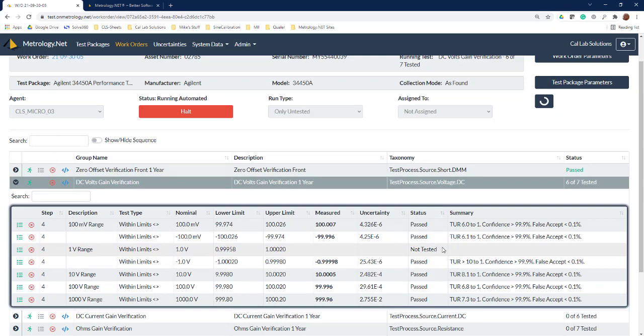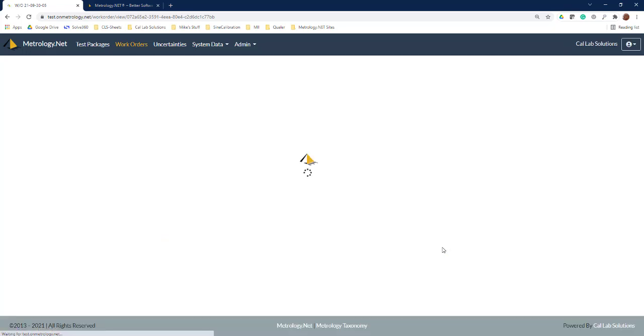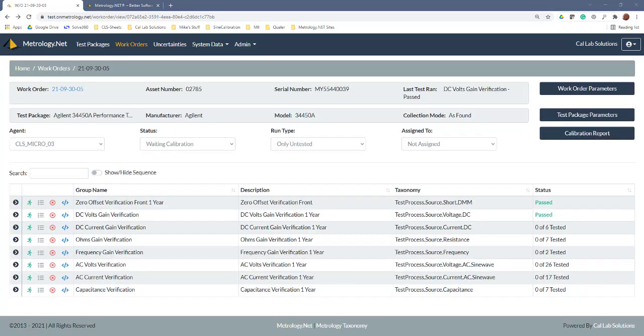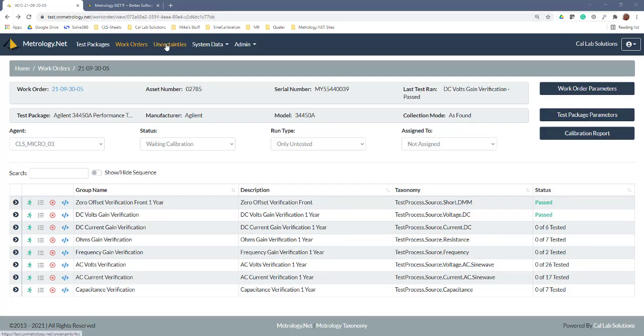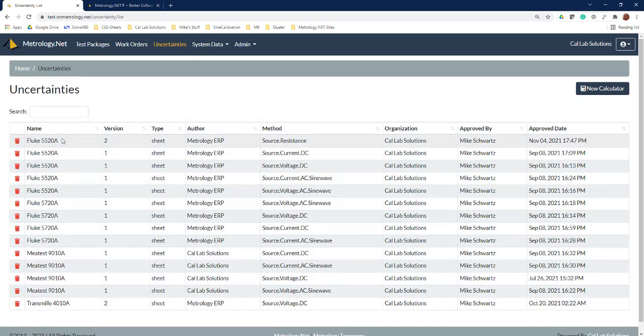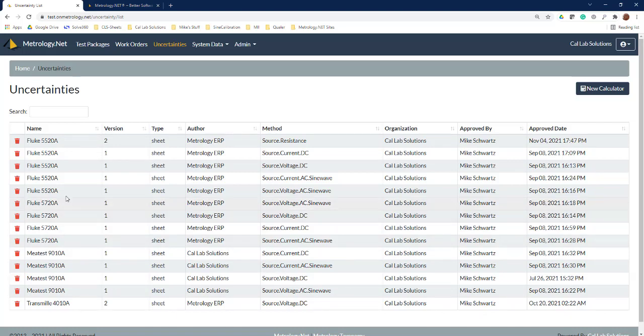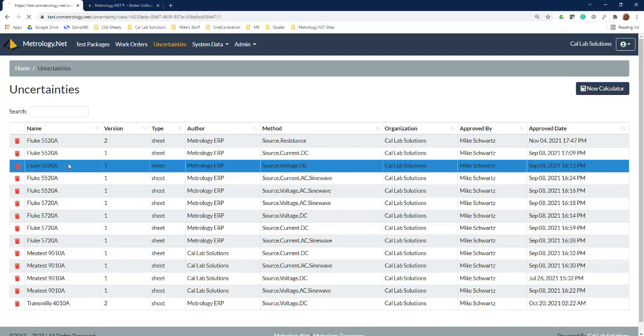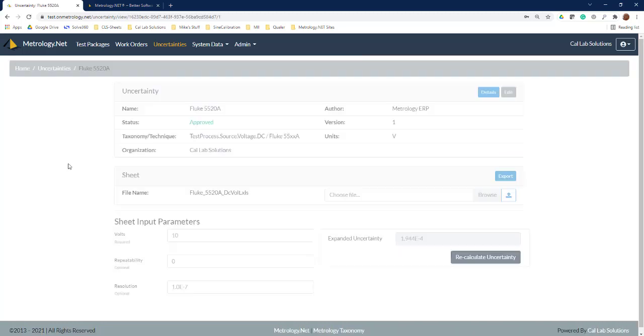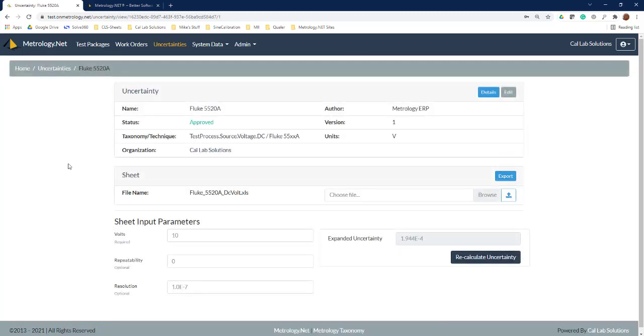Now let's take a quick look at how we're doing measurement uncertainties in metrology.net. Up here we've got an uncertainties tab, so I'm going to click on this and then we're going to search down the side for our 5520 DC voltage. You see right here we have our 5520 source volts DC, so I'm going to go ahead and click on this.